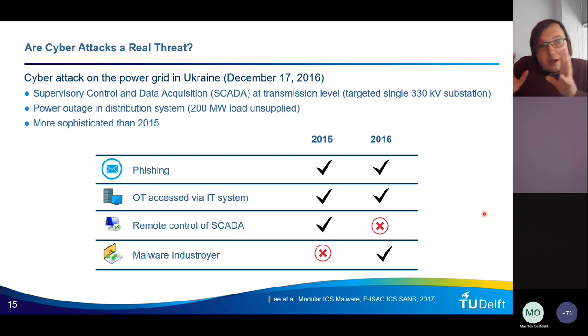And here we have a slide where we are asking ourselves, are cyber attacks a real threat, especially on power grids? Well, let's look at the incident that happened on December 17, 2016. There was a cyber attack on the power grid in Ukraine, and the attack targeted the supervisory control and data acquisition, so the SCADA system, at transmission level. The attackers targeted a single 330 kV substation, so a big substation, but the impact of the attack was felt in the distribution system, where 200 megawatts of load was not supplied. This was a more sophisticated attack than 2015, and here we have a comparison. Just a very brief comparison, there's no point in going into too many details.